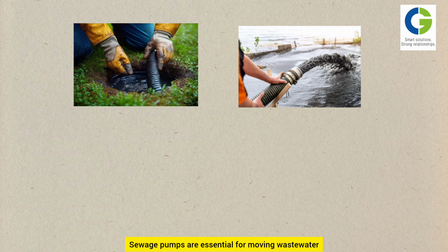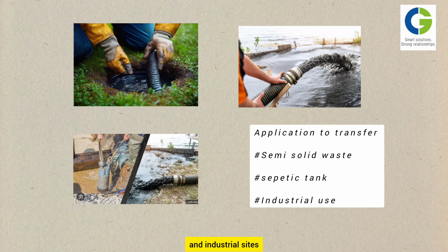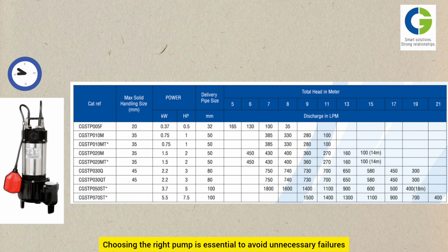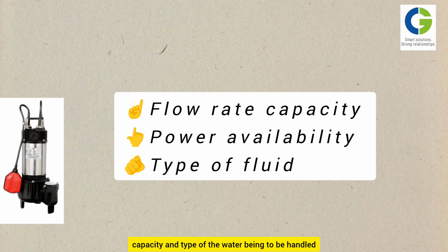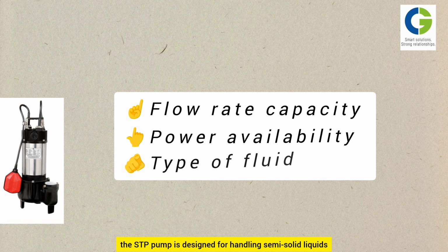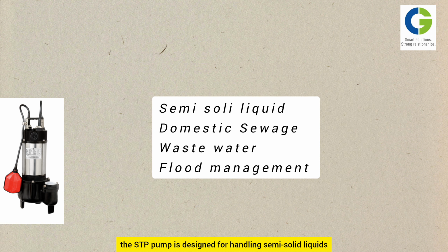Sewage pumps are essential for moving wastewater that contains semi-solid waste from homes, hotels, restaurants, industrial sites, or septic systems. Choosing the right pump is essential to avoid unnecessary failures. The right pump depends on factors like flow rate, capacity, and the type of water to be handled. The STP pump is designed for handling semi-solid liquids, sewage, and wastewater.